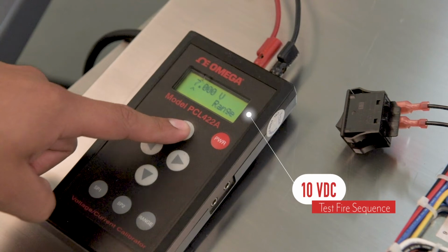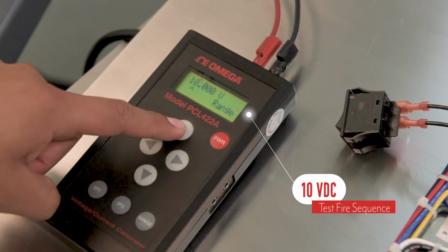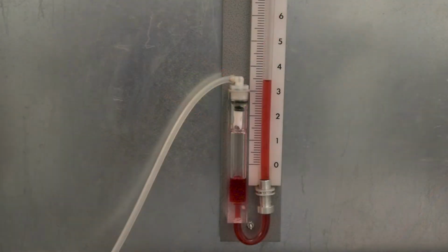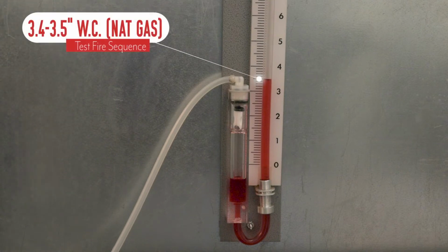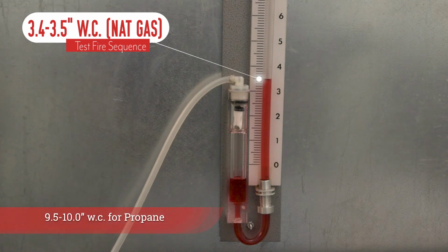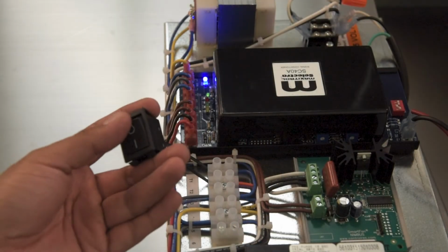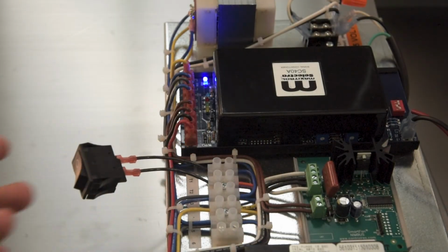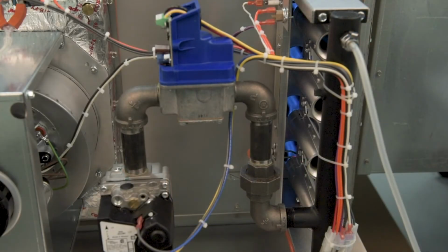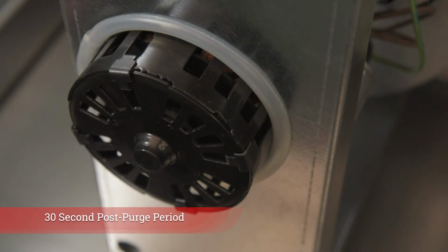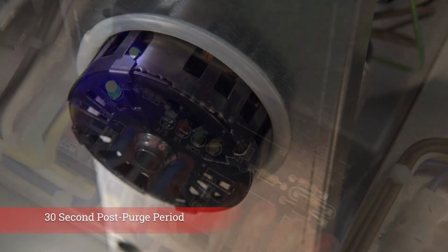Increase the modulation signal to 10 volts DC to the SC40. Verify the high fire manifold pressure has remained 3.4 inches to 3.5 inches water column for natural gas or 9.5 inches to 10.0 inches water column for propane. Remove the call for heat by opening the heat enable switch. The combination gas valve will close, shutting off the supply of gas to the burners. The flames will extinguish and the inducer will start its 30-second post-purge period.